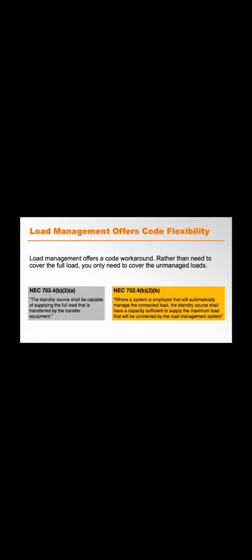It's also worth noting that load management can provide a clean solution to compliance problems. If your AHJ enforces NEC 702, then you may have had to be very strict with the way that you size your sub panel. You may have had to sell more storage than you wanted to cover loads. Well, there's a second part of this code, part B, that basically says that if you have a load management system in use, the battery only needs to be as big as the maximum load that will be connected or transferred by the load management system. The load management system, remember, prevents the local load from exceeding the battery's capacity.